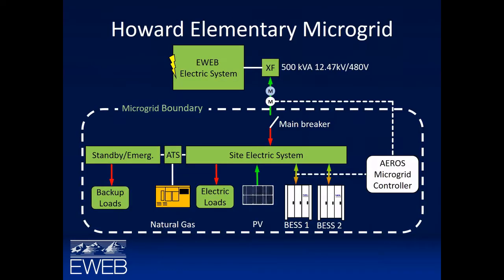The system right now has about 50 kilowatts of PV, and an ATS system with an 80 kilowatt natural gas generator. We decided not to integrate with the gas for charging, just due to complexity, so we left the ATS scheme alone. You can see here we have two battery systems, BESS1 and BESS2, both controlled by the onboard AEROS microgrid controller that NEC makes. The main disconnection point is at that main breaker, at the main panel.